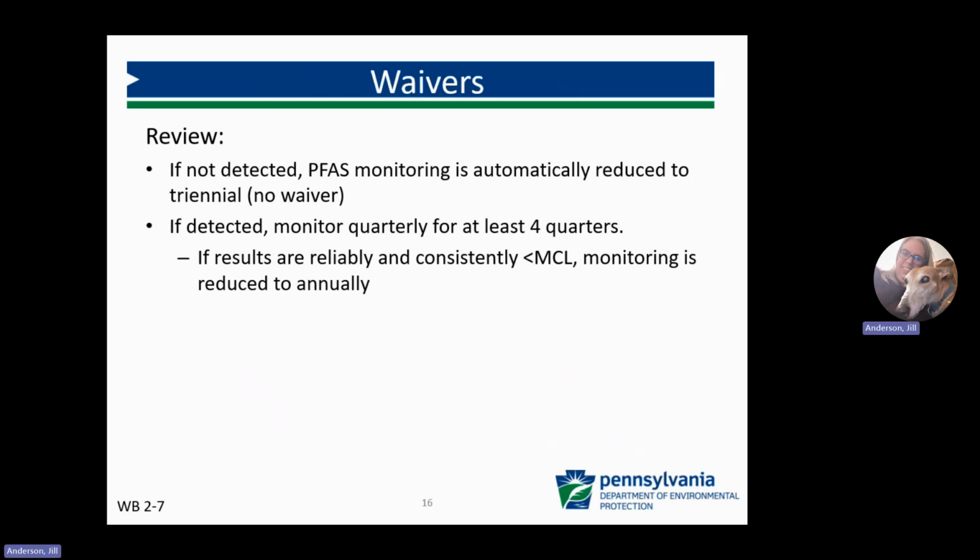If a PFAS is detected, monitoring is required quarterly for at least 4 consecutive quarters. And if results from 4 consecutive quarters are reliably and consistently below the MCL, monitoring is reduced to annually. And again, no waiver is required for this reduction.